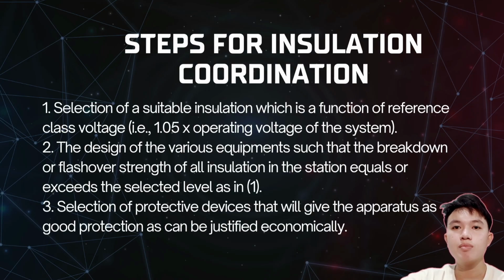So the final step is selection of protective devices that will give the apparatus as good protection as can be justified economically. Finally, you choose protective devices like surge arrestors that offer the best possible protection for the equipment. The choice is a balance between maximum safety and what is economically justified, ensuring the system is safe without overspending on unnecessary specs.